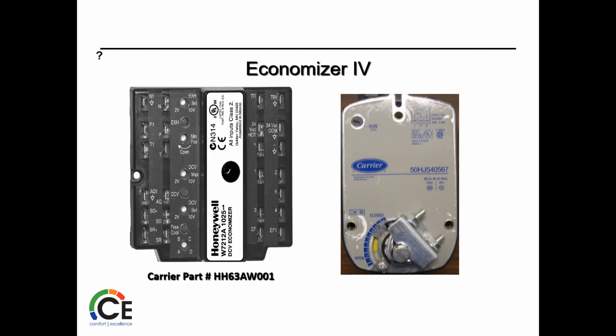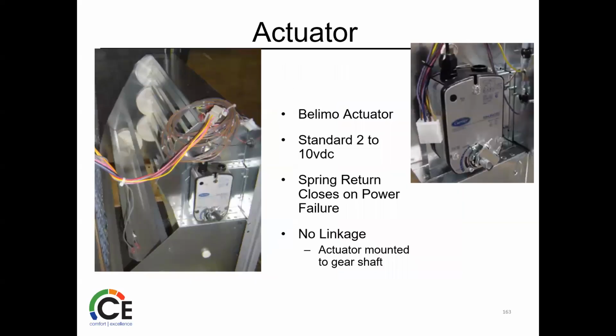So again, here you'll see this Economizer 4. That's definitely a Carrier Bryant name for it. It's got its own part number, but it's a very popular one that's out there. You see Economizer 4. You also see Economizer X. So, important information for later. The motors do have an over torque sensor. When closing, it will sense if something's tight and it'll stop. So maybe some debris got in there or something, who knows. So that's there to protect your actuator motor.